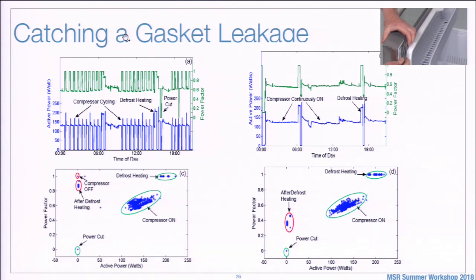Because of the gasket leakage, the refrigerator wasn't cooling sufficiently, so the user didn't notice anything wrong since it seemed to work fine. But it was never going into compressor-off mode because the thermostat couldn't activate it. You can see it's always on with no on/off cycles. Looking at the clustering, the compressor-off state that should appear periodically was completely missing from the actual operational model.